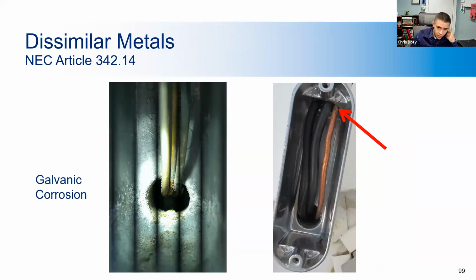So many contractors underestimate the effects of galvanic corrosion that happens with the direct contact of dissimilar metals. You can see that starting way up here on the right, and you can see it well underway on the left. So the copper conductors are in contact with a dissimilar metal in a wet location, and you can see that they're corroding and deteriorating. A way to avoid this would be to use insulated conductors or other methods to prevent the touching of those two metals. This one isn't that bad yet, but it will continue to get worse and worse until it corrodes away, and then you don't have a ground path.